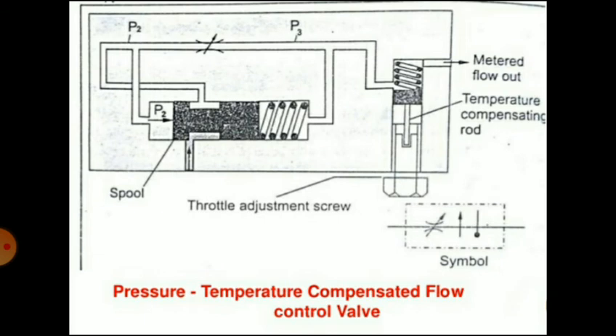The third category is the pressure-temperature compensated flow control valve. The pressure compensated flow control valve maintains nearly constant flow despite variation in circuit pressure, but there is another parameter which affects flow: temperature. The effect of temperature is that the viscosity of oil decreases, causing oil to become thinner, which leads to increased velocity and hence increased flow. The principle of operation is that an increase in temperature causes a decrease in viscosity, which causes an increase in velocity. To keep flow constant despite increased velocity, the flow area A must be reduced. This is achieved by a special alloy rod which expands and contracts on even small variations in temperature.